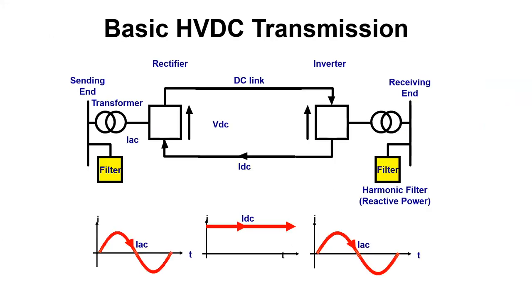This slide shows the basic HVDC circuit. It has a sending end converter for conversion of AC power to DC power, then the DC transmission circuit for carrying DC power between ends, and finally a receiving end converter for conversion of DC power back to AC power. Between the AC grid point and the converter point at both ends, there is a transformer, which has technical reasons, such as providing electrical isolation between AC and DC, limiting fault current, providing reactance necessary for the working of the converter, and so on.